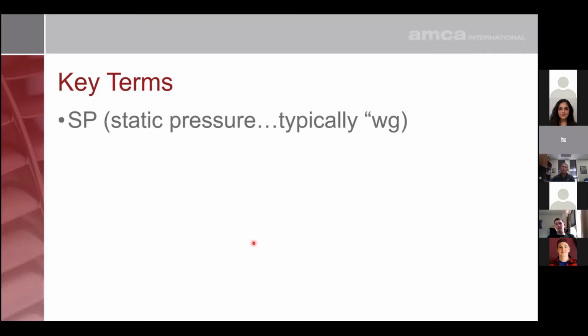Second key term is static pressure, or the resistance that the fan has to overcome when moving that required volume of air. In the United States, we typically express it as inches of water gauge. You need 27.7 inches of water gauge to equal 1 PSI. It's a relatively small number. So to inflate car tires, you need to have about 900 inches of water to inflate your car tires to nearly 30 PSI. So just kind of giving you some reference there.